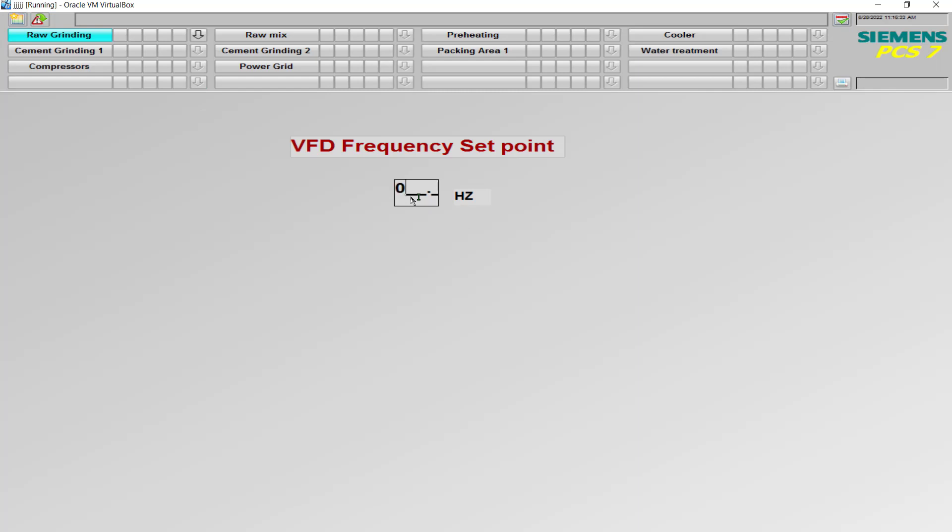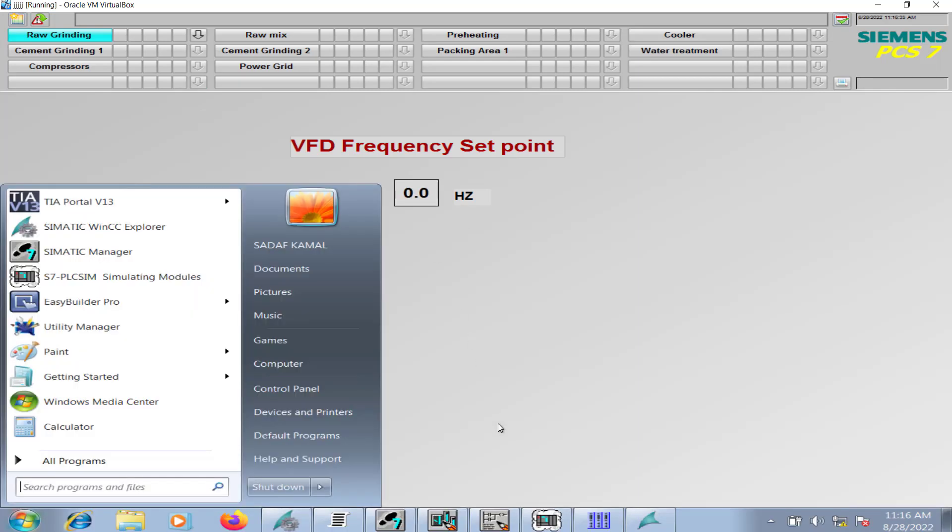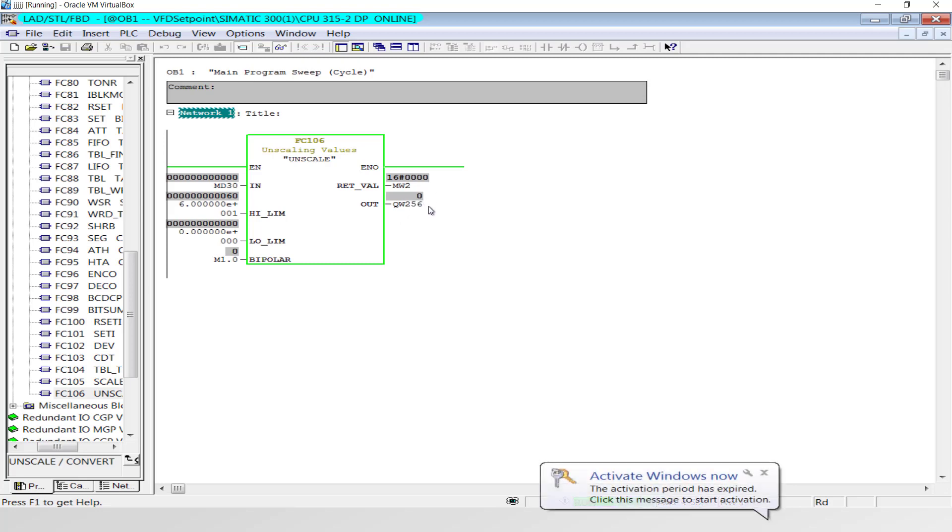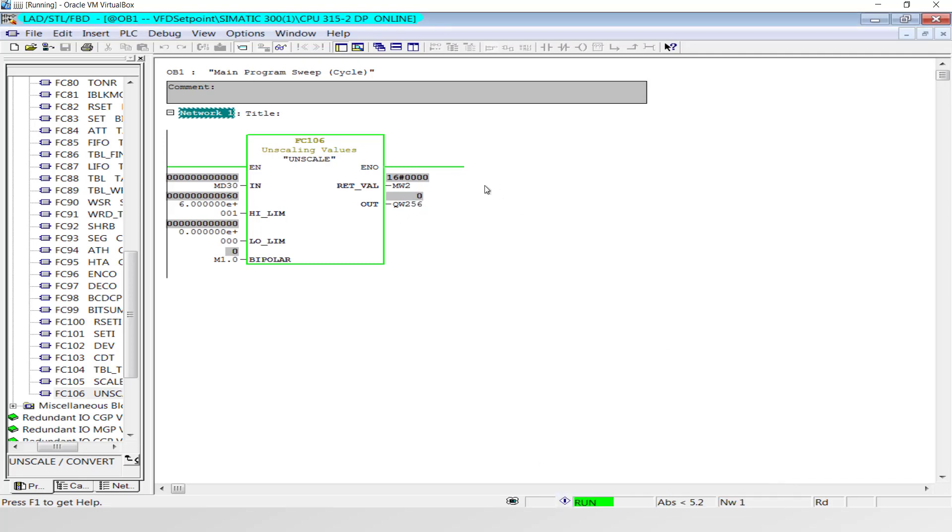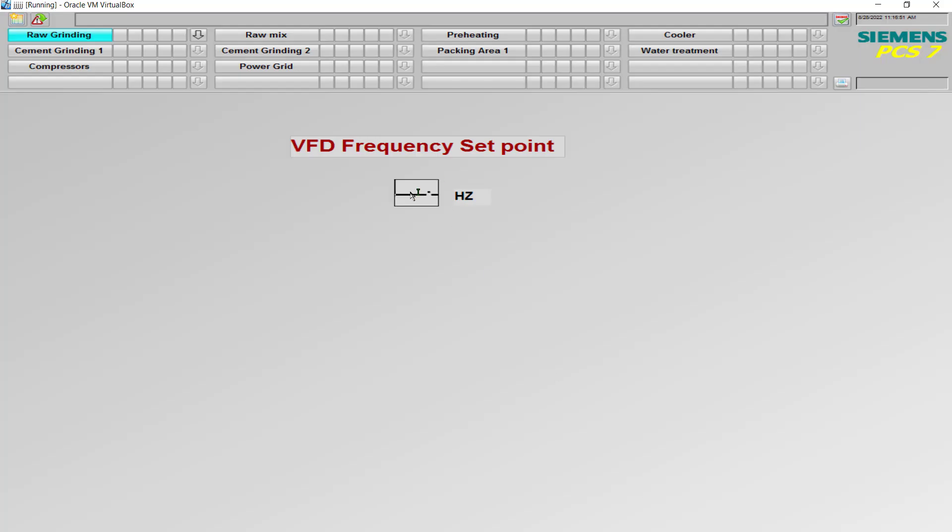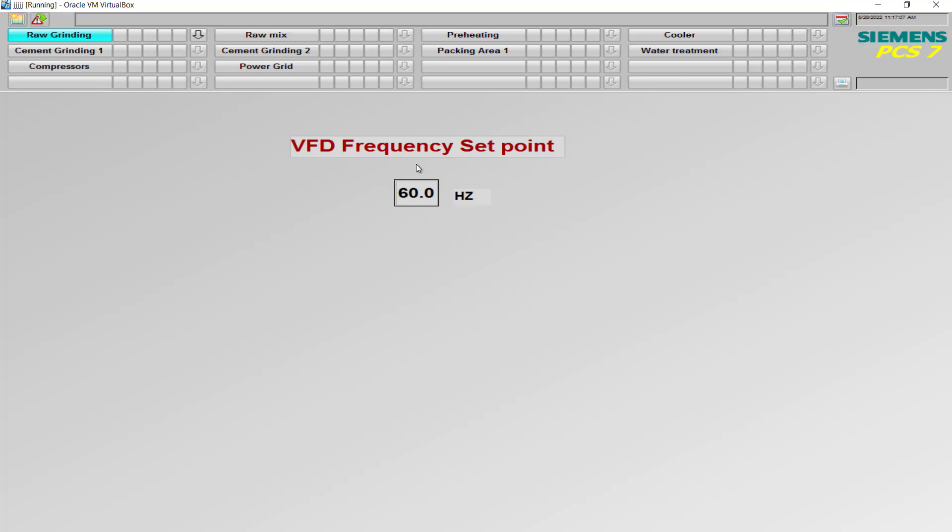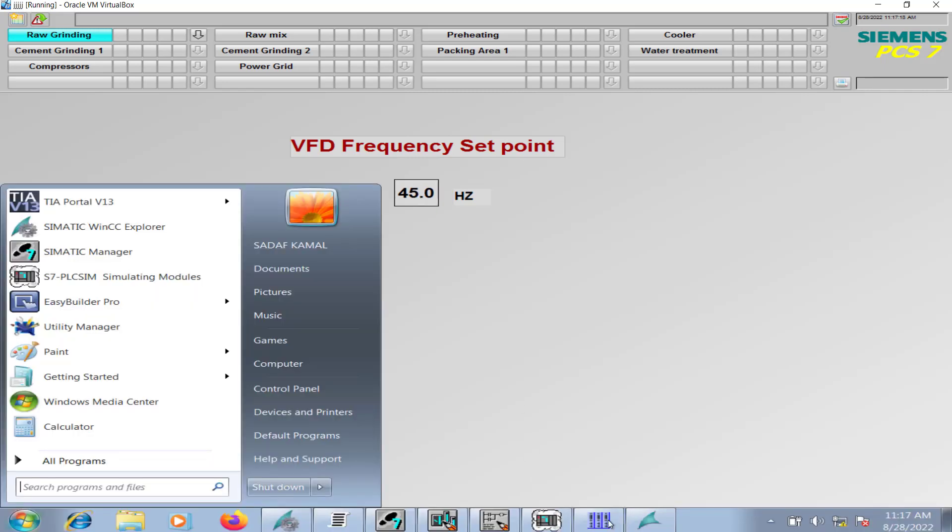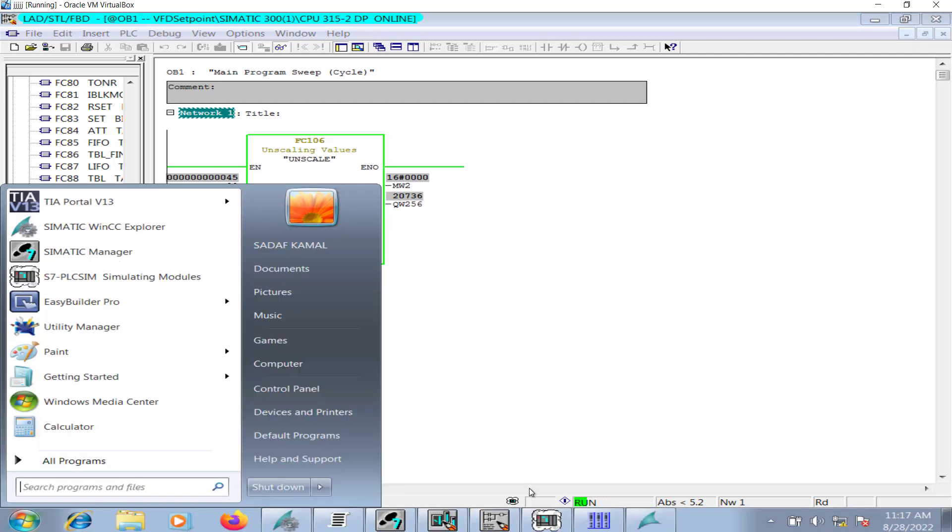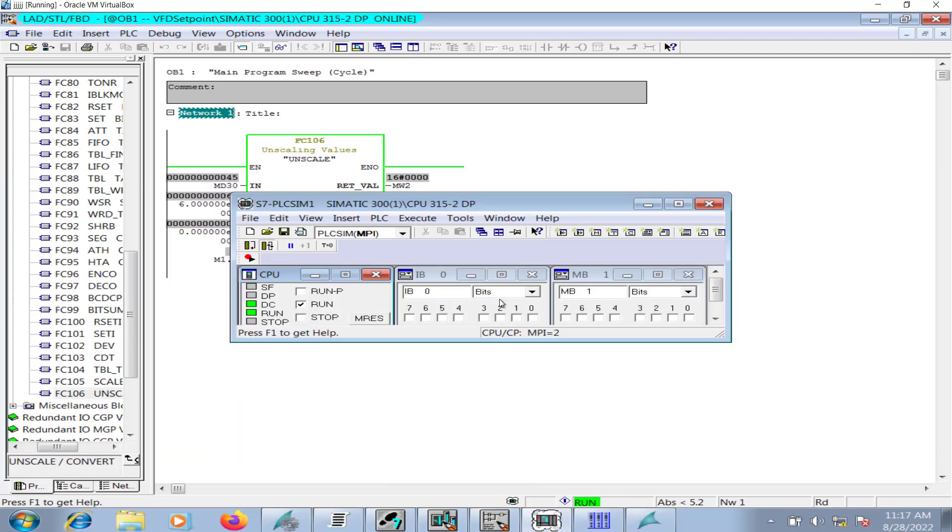Let me enter zero Hertz. No value is being output, that is 4 milliampere would be output from the analog output channel, since the minimum value is 4 milliampere. If I enter 60 Hertz, 2 7 6 4 8, that's the maximum value, that is 20 milliampere in this case that is being output by the AO card of the PLC. Any value in between would be scaled accordingly. For example, 30, for example 45 Hertz. Go to the OB1, 2 0 7 3 6.